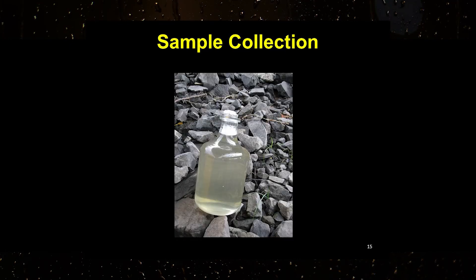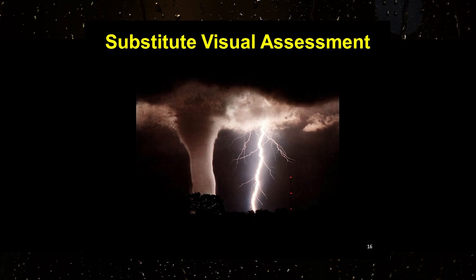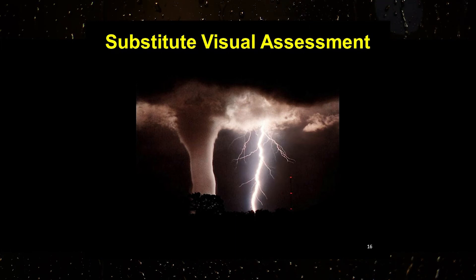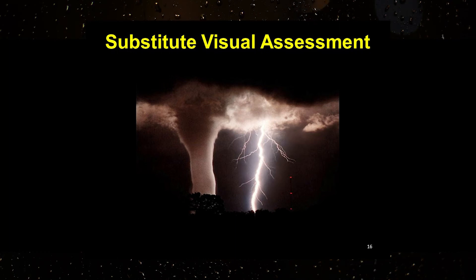Samples will need to be collected in a clean, clear container for visual assessment. Should adverse weather conditions create inaccessibility or dangerous conditions for personnel, a substitute visual assessment shall be conducted during the next qualifying storm event. Other adverse conditions include extended dry periods or extended cold periods where there is no snow melt. If you miss a qualifying event, you shall collect the visual sample during the next qualifying event, and the reason for the alternate sample must be included in the visual assessment documentation.